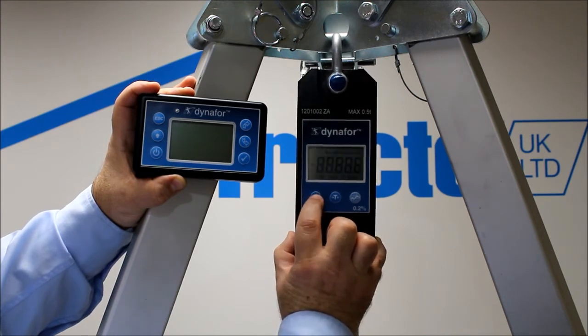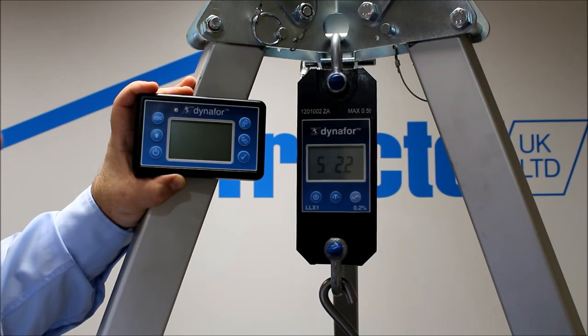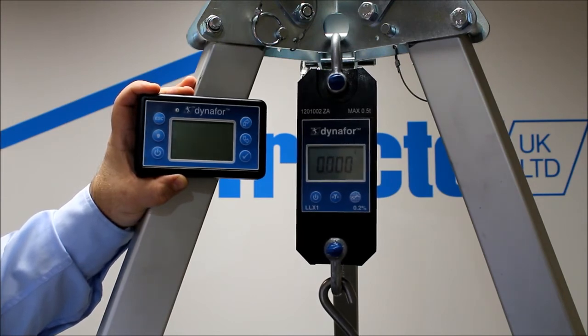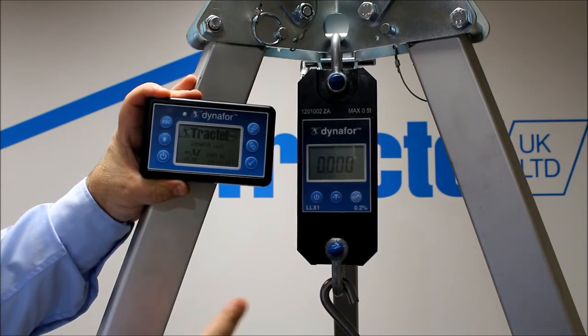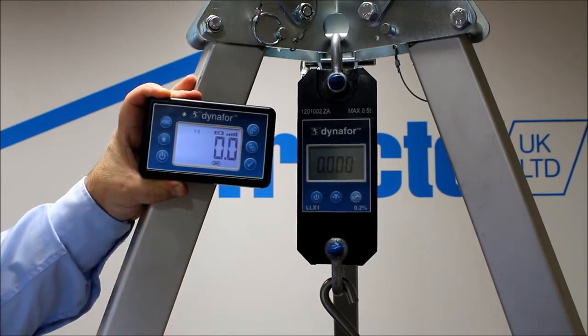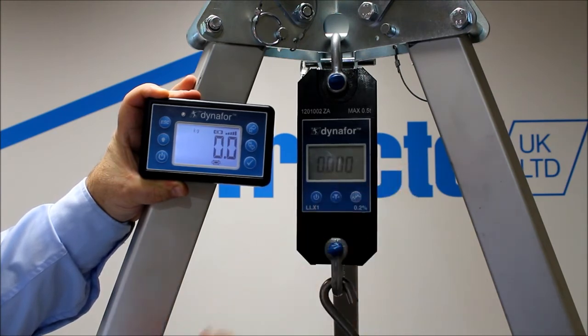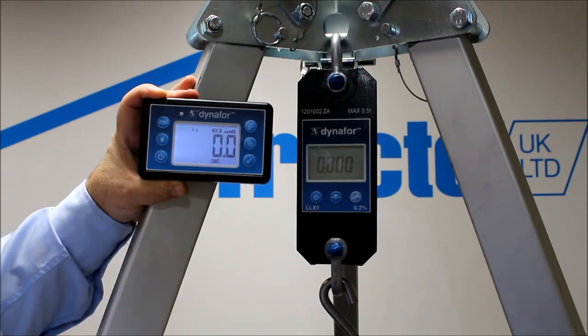You turn the load cell on first and let it go through its startup functions. When it gets to zero, you can turn the handheld display on. The handheld will then pick up the zero from the unit. It has a backlight function to make viewing a lot easier. As you can see from the display on the Dynafor, it's flashing — meaning all the functions are basically being stored and held in the handheld display.